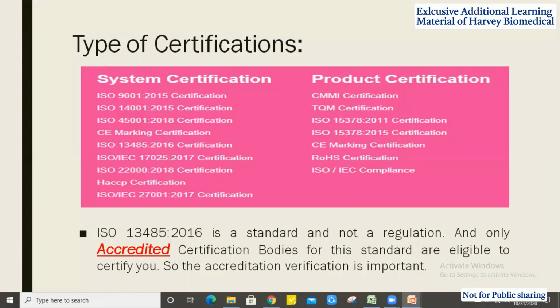You can see ISO 13485:2016 is a standard and not a regulation. A standard means it's a procedure, and regulations mean the company should follow the specific regulations, govern by them, and strictly implement them. With a standard, in some cases we can exclude some of the criteria based on our manufacturing facility and our product. Only accredited certification bodies for this standard are eligible to certify you. It means whenever a certification body is accredited, only then can that certification body give the ISO 13485 certification. Otherwise, they are not able to.